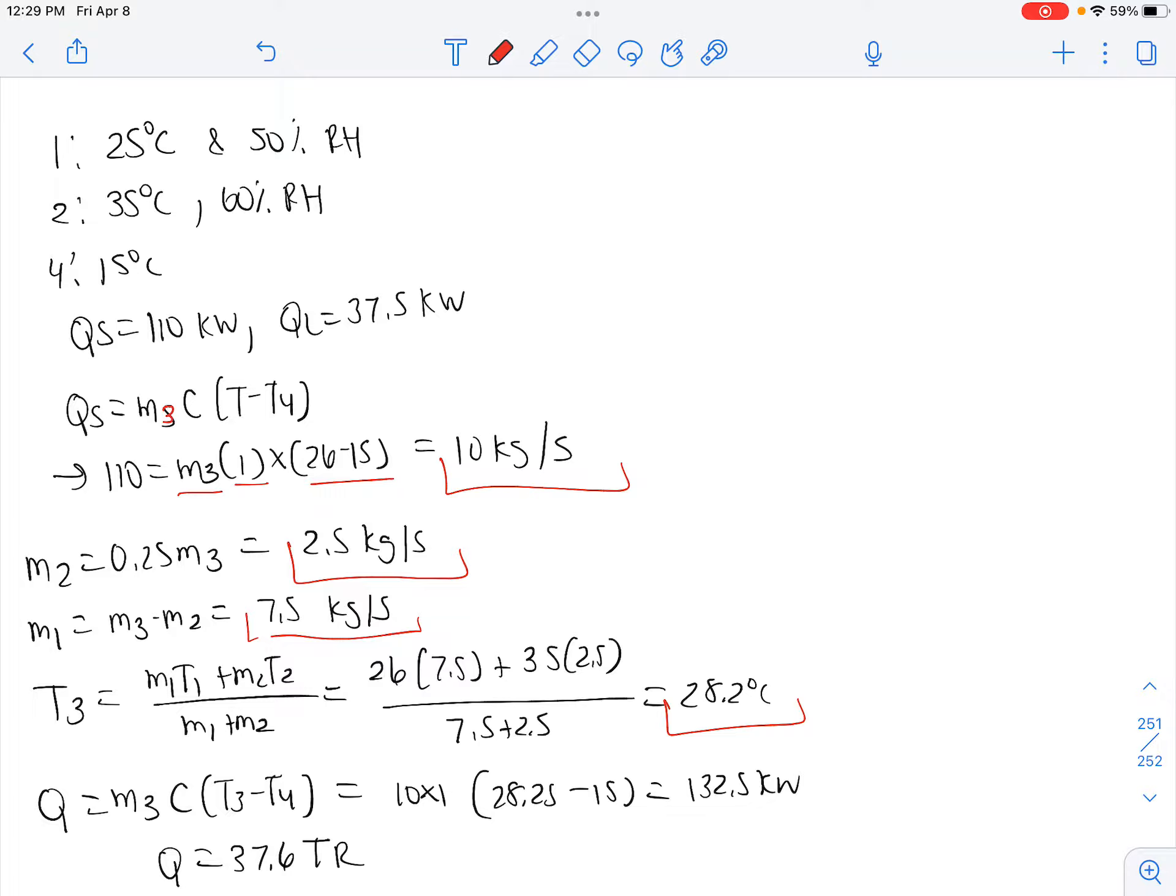So our refrigeration capacity Q is M3 times C times T3 minus T4, or 10 times 1 times 28.25 minus 15, which is 132.5 kilowatts. But one kilowatt is 0.2843 TR, so our Q is 37.6 TR.